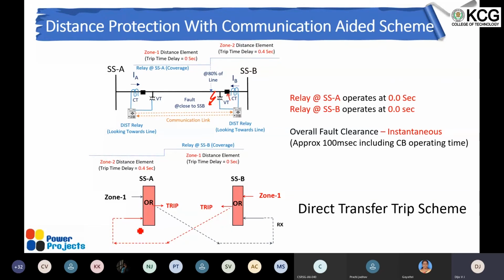That part comes here, and even though zone 1 of this relay did not operate, that's the relay at substation end A, since it is getting a communication feedback or some communication signal from the remote end, it goes for tripping, right? So the only additional time delay will be the communication time delay, which is caused to communicate the digital trip signal from this point to this point. We can consider it as 5 to 10 milliseconds. So this relay will operate at 100 milliseconds, and this relay also operates very close to 100 milliseconds.